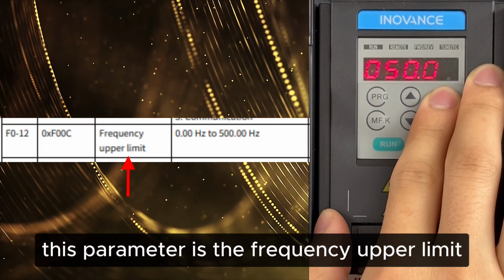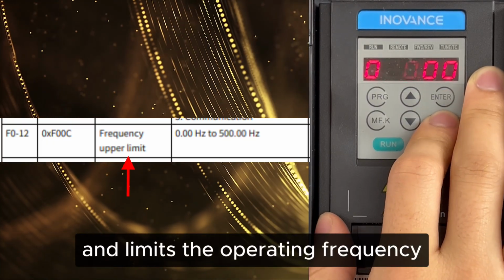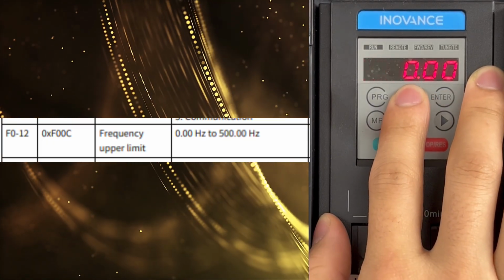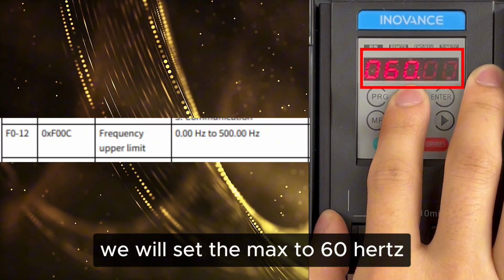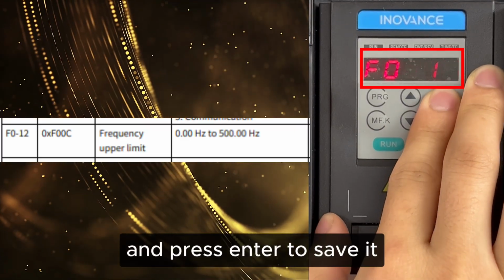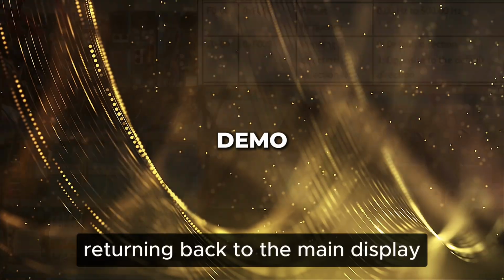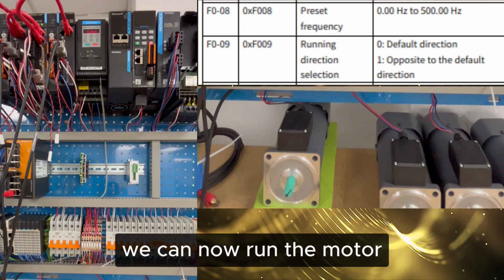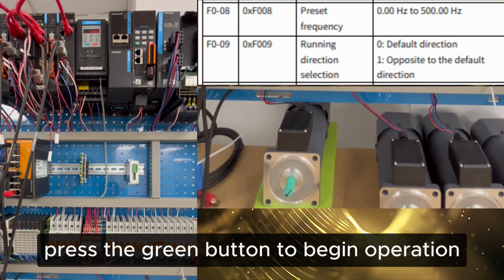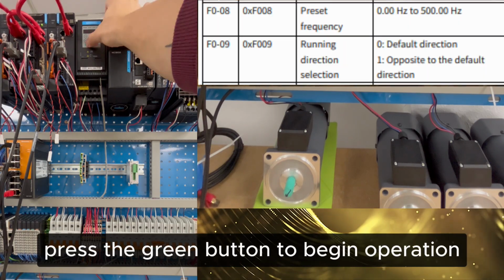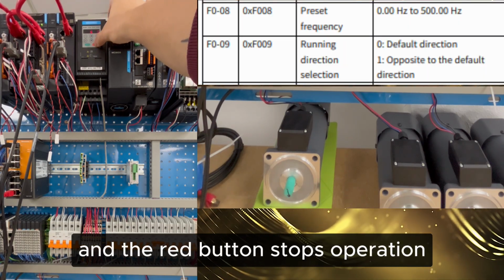This parameter is the frequency upper limit and limits the operating frequency of the motors. For our example, we will set the max to 60 Hz and press Enter to save it. Returning back to the main display, we can now run the motor. Press the green button to begin operation and the red button stops operation.